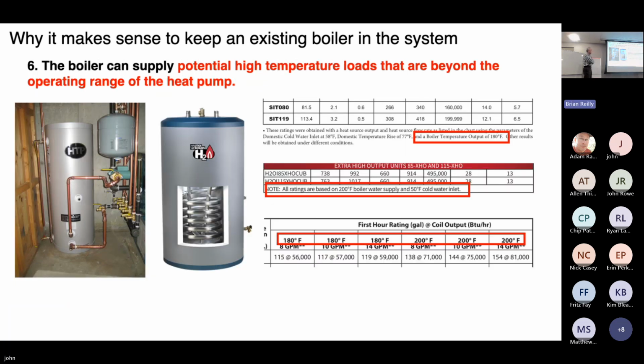Again, there are loads, and I pointed at these indirect tanks. One of the characteristics of indirect water heaters is that over the years, when these things were developed, they were developed around boilers. This is a classic one. These are the connections on the coil. The coil is just in the bottom of this tank. These coils were sized by the manufacturer assuming anywhere from 180 to 200 degree water. These coils are not very good heat exchangers when they're brand new. What happens to that coil over the years if you've got any kind of solids in your water, magnesium, calcium, that type of thing? They scale up, and when scale forms on the domestic water side of the coil, the heat transfer goes down even less.